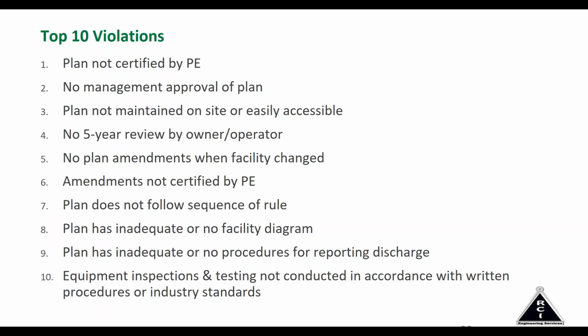The last one, number 10, is one that will probably be the focus of future webinars. Equipment inspections. This is one that gets most of the regulated facilities that we've been involved with, and that is that equipment inspections are required to be conducted on a monthly basis. In addition to that, there may be some testing required of the storage containers, and they have to be done in accordance with the industry standards I spoke of earlier, the Steel Tank Institute standard or the API standard.